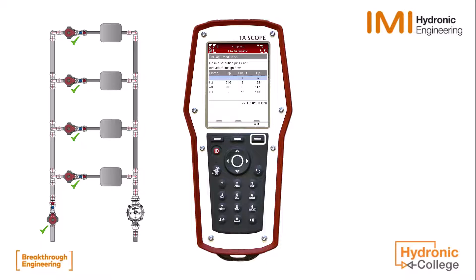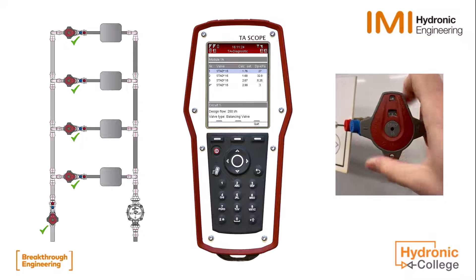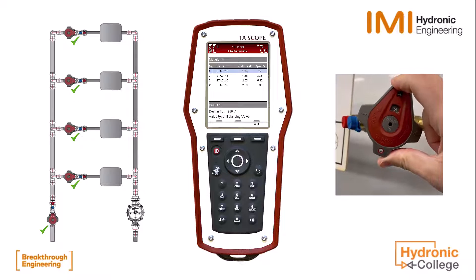Press quit to view the calculated pre-settings for the balancing valves. Here we can see the calculated pre-setting in the balancing valves required to achieve an optimal balance. Take note of these figures and pre-set the valves accordingly.